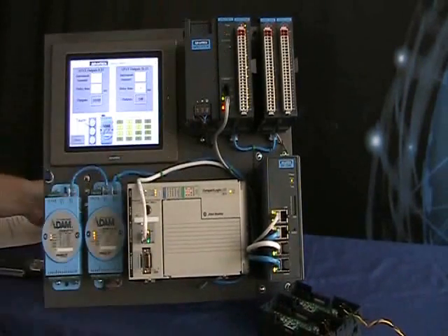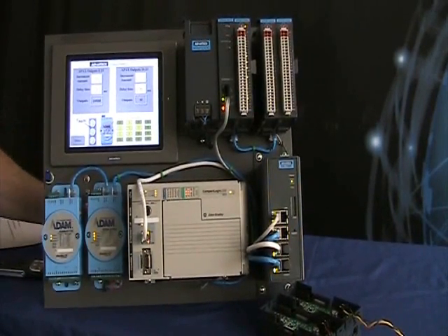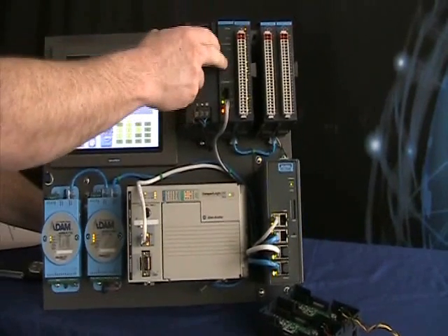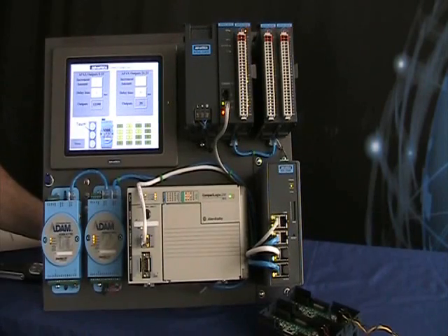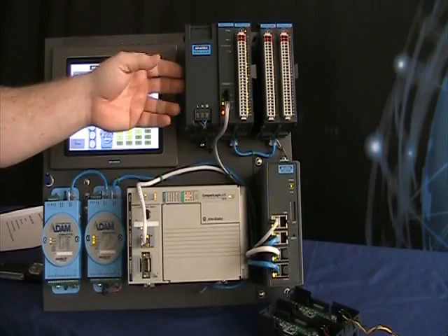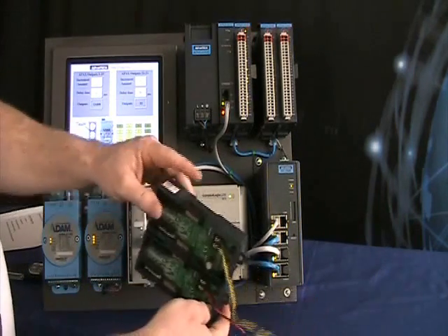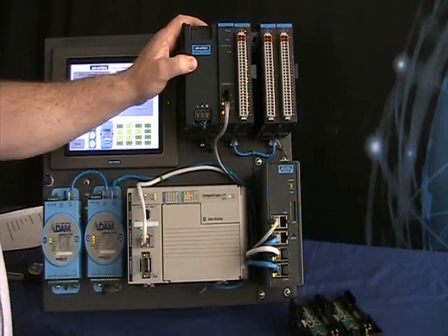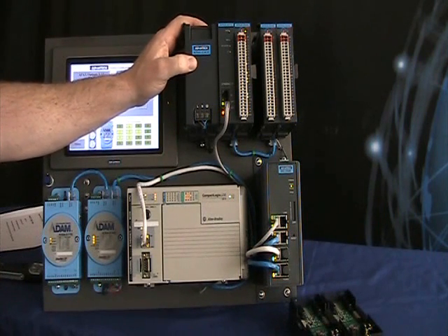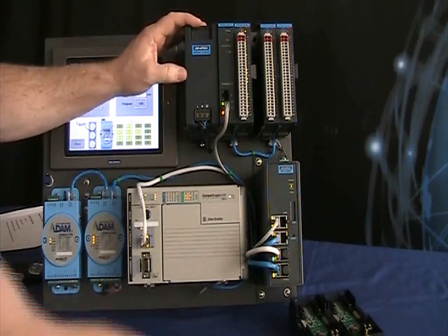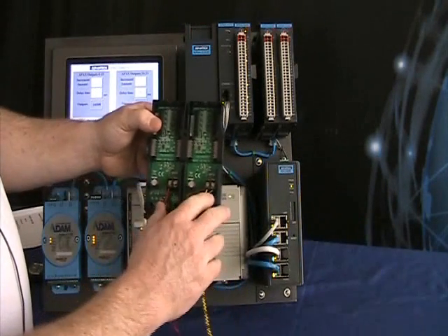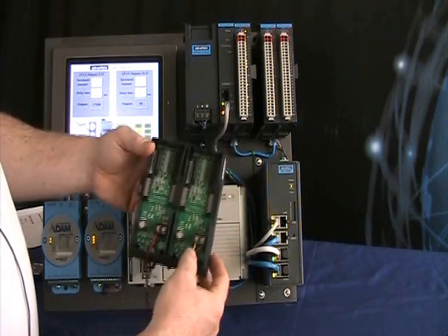Now we have other couplers in this product line as well. There is a WinCE-based controller which is its own PAC controller. We have a Modbus TCP coupler and we also have a Profinet coupler. What you see here, which is connected directly to the backplane through this connection right here, is a power supply. This power supply will support up to 72 watts at 24 volts. If you don't want to use this power supply or if you have remote I.O., you can see from the backplane that you can connect your power to any of the backplane that are on the network.